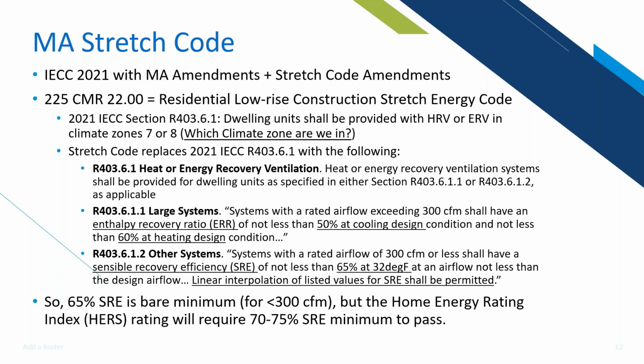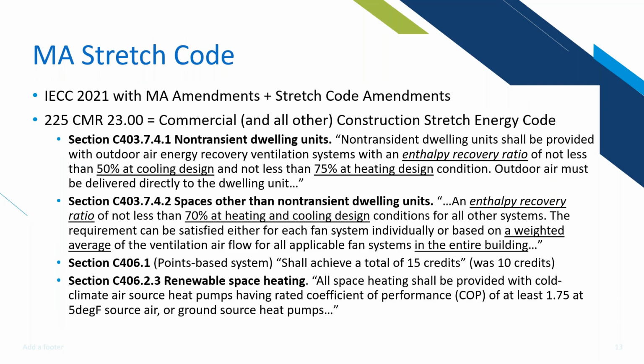So moving on to the commercial side of this, the 225 CMR 23, which is the commercial and all other construction stretch energy code, there are a few different amendments worth noting. One, in non-transient dwelling units, you should get an enthalpy recovery ratio of not less than 50% in cooling and 75% in heating. So in the winter, you must get a higher enthalpy recovery ratio.